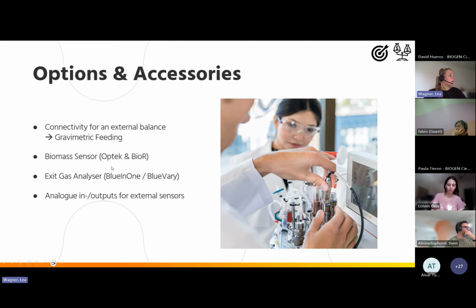Then we have an exit gas analyzer available from the manufacturer BlueSens, and we have the BlueInOne and the BlueVary in different combinations depending on what the customer needs, or if the customer has a cell culture or microbial process. And the exit gas analyzer gives the customer a hint about the metabolic activity of the process. Deeper insight into the process, and in combination with Eve, the oxygen uptake rate can, for example, via soft sensor be calculated, or the carbon evolution rate and the respiratory quotient, which gives the customer deeper insight into the bioprocess.